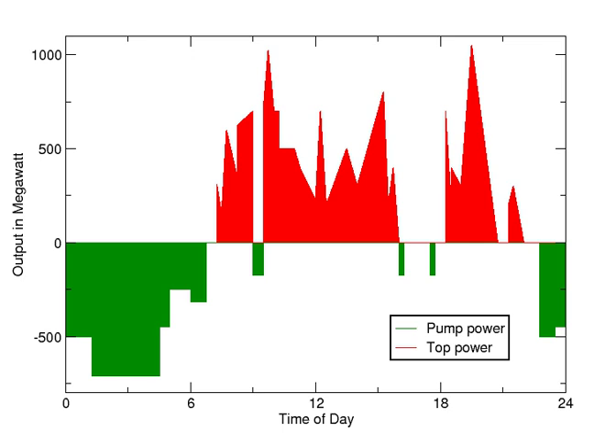Transmission of electricity between the reservoir and the grid can be established from a nearby offshore wind farm, limiting transmission loss and obviating the need for onshore cabling permits. A current commercial design featuring a sphere with an inner diameter of 30 meters submerged to 700 meters would correspond to a 20 MWh capacity which, with a 5 MW turbine, would lead to a 4-hour discharge time. An energy park with multiple such reservoirs would bring storage cost to around a few euro cents per kWh, with construction and equipment costs in the range of €1,200 to €1,400 per kW. To avoid excessive transmission cost and loss, reservoirs should be placed off deep water coasts of densely populated areas such as Norway, Spain, the USA, and Japan. With this limitation, the concept would allow for worldwide electricity storage of close to 900 GW hours.